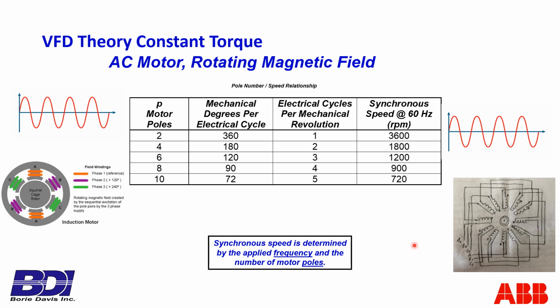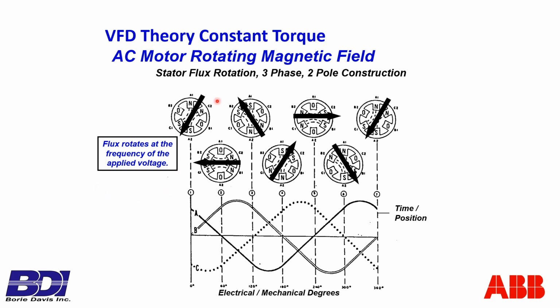That's why that math equation we did on torque said that there was 3 foot-pounds per horsepower of torque available on a 1,800 RPM motor, and only 1.5 on the 3,600 RPM motor. And then, of course, the applied frequency is 60 hertz, and the applied voltage 460. Okay. Here we have the actual, trying to share with you how the motor rotates.